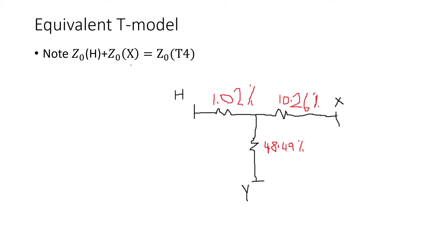So here's the equivalent T-model. Basically the T-model, you have the high side, the midpoint, then you have the low side, then you have the tertiary or the Y side. So for the H side I got 1.02%, for the low side I got 10.26%, for the Y I got 48.49%.